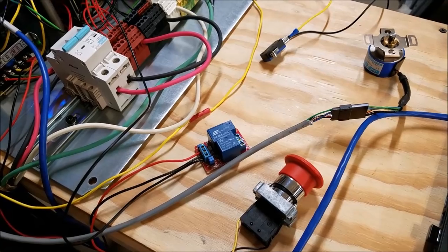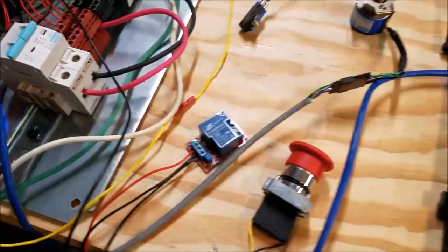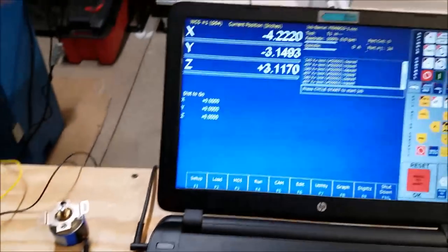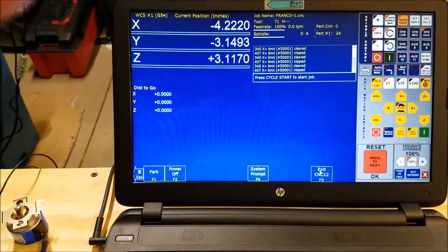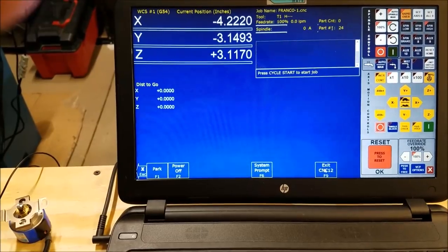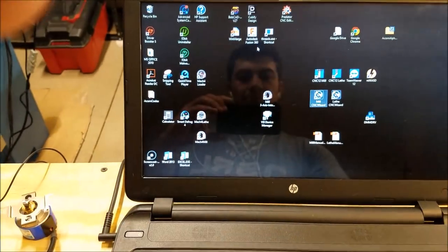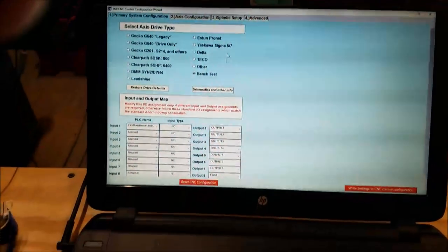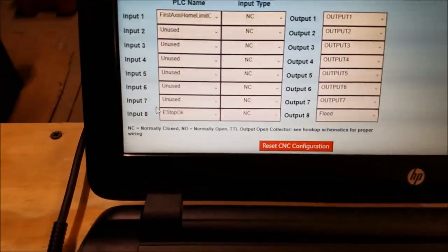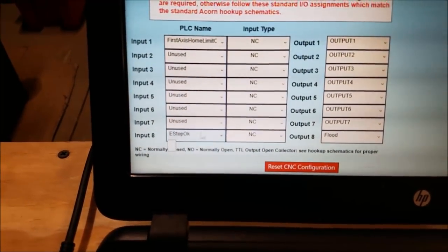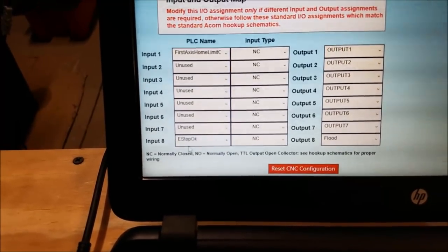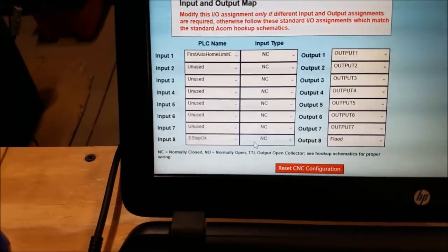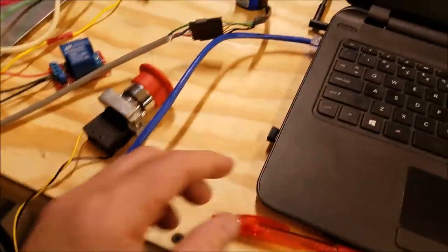So there is your first connection. We are coming out of input 8, 24 volts, all the way here to the e-stop, and then black wire returning to common. That will give you your e-stop. Let's look at the wizard here really quickly. You can see I have input 8 set to e-stop, normally closed connection. So that's how you typically wire your e-stops, is a normally closed connection.